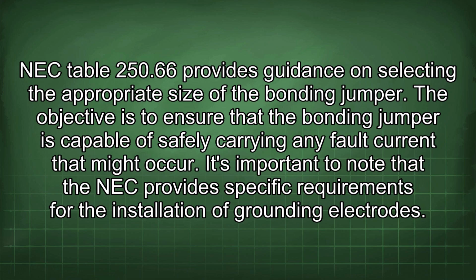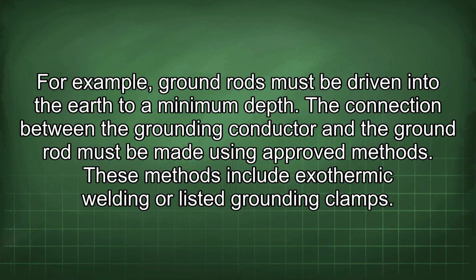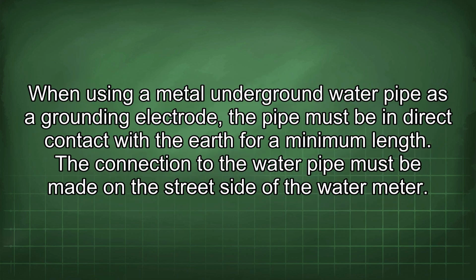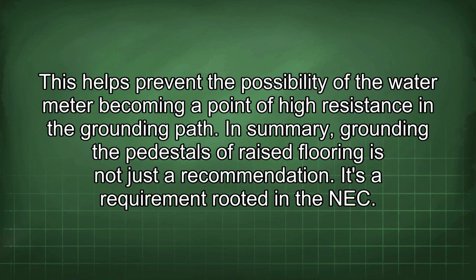It's important to note that the NEC provides specific requirements for the installation of grounding electrodes. For example, ground rods must be driven into the earth to a minimum depth. The connection between the grounding conductor and the ground rod must be made using approved methods. These methods include exothermic welding or listed grounding clamps. When using a metal underground water pipe as a grounding electrode, the pipe must be in direct contact with the earth for a minimum length. The connection to the water pipe must be made on the street side of the water meter. This helps prevent the possibility of the water meter becoming a point of high resistance in the grounding path.